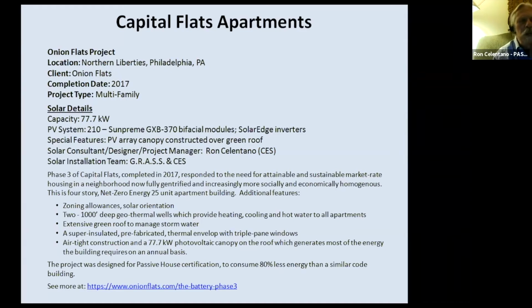Now this is a pretty unique system. It's a 4-story, about 25 unit apartment building, and it had ground source or geothermal heat pumps, with an open well going down into the Delaware River, pulling water from the river into the heat pump HVAC system, which then circulated into a heat pump water heating structure for domestic water heating. Any discharge water, or water that came up through the river, would go through that first. So it was really very efficient at utilizing that heat, or cool, for hot water.